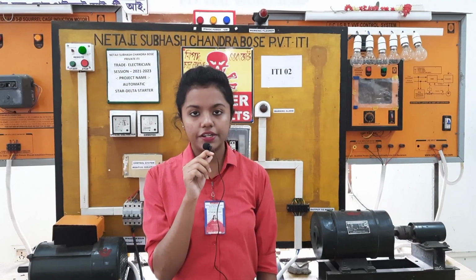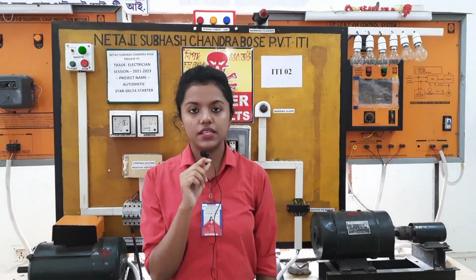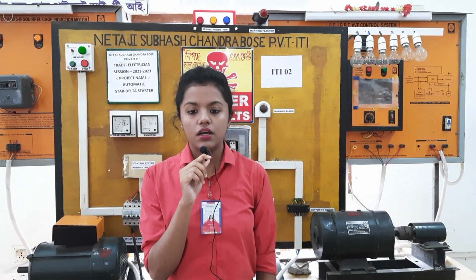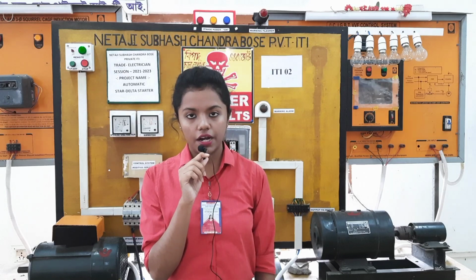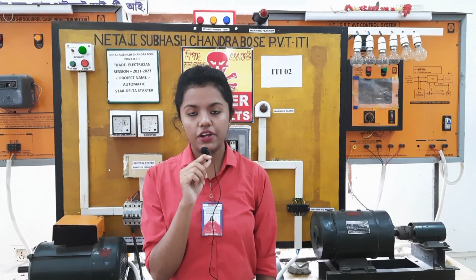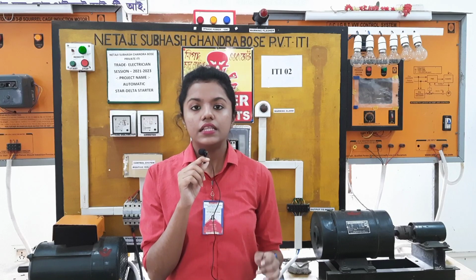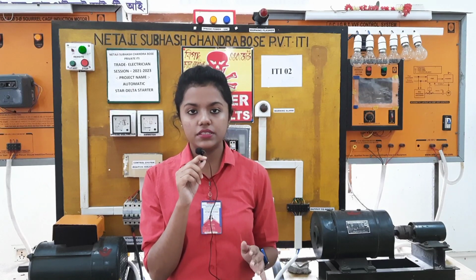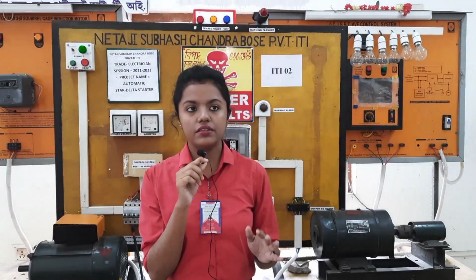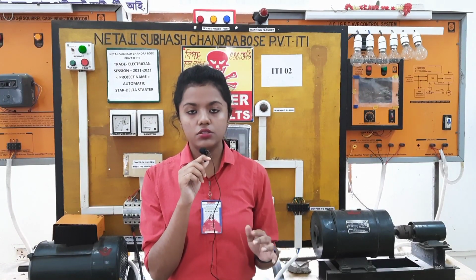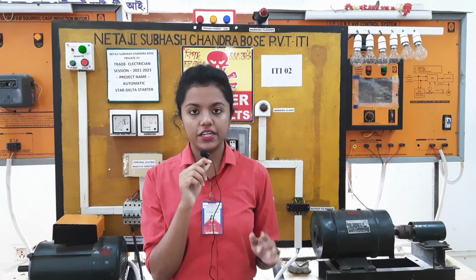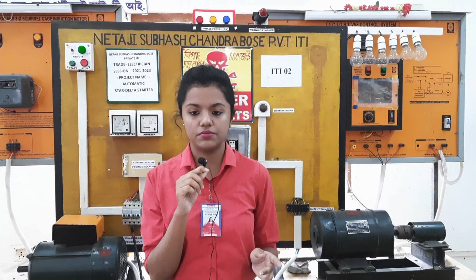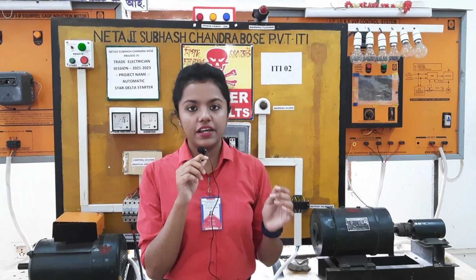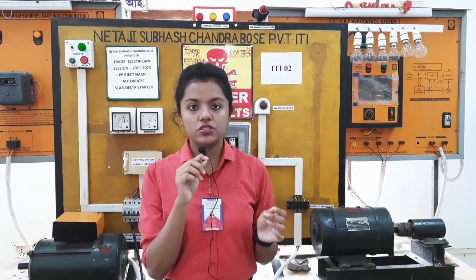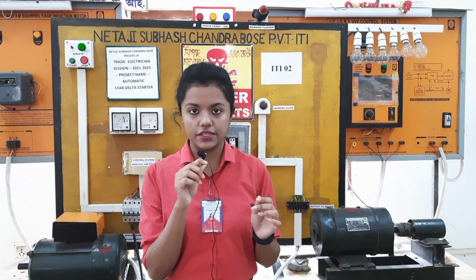At the time of starting, the motor rotor is at standstill and the slip is large, which causes a large inrush of armature current, which is 6 to 7 times of full load current. This large current can damage the stator windings and burn the motor, and also lead to voltage dips on the supply lines. To avoid these unwanted effects, we use star delta or auto transformer starter.